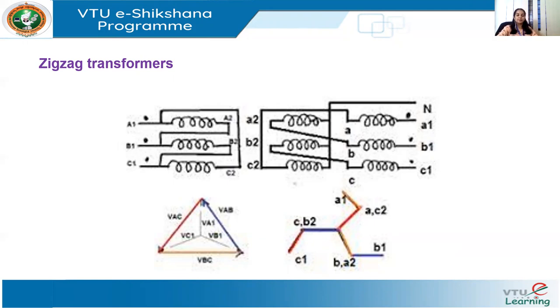We have seen two methods here: the inline choke, connected mainly with adjustable speed drives, and the zigzag transformer, which can be connected to any commercial facility. We are going to stop here, and in the next class we will see more devices used for mitigation of harmonics — mainly active and passive filters. Thank you.